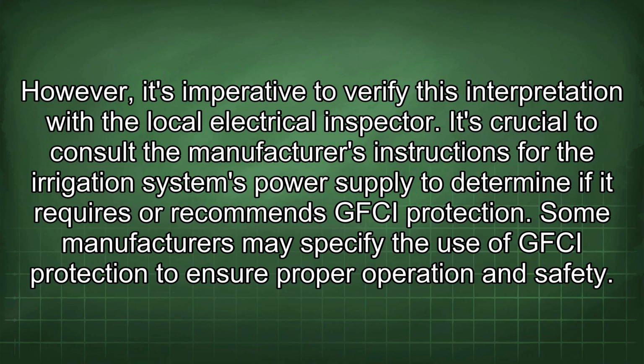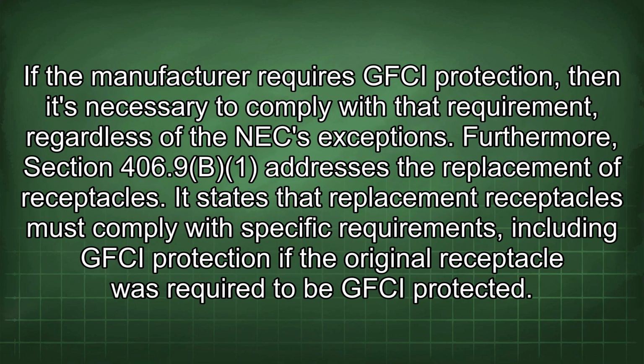It's crucial to consult the manufacturer's instructions for the irrigation system's power supply to determine if it requires or recommends GFCI protection. Some manufacturers may specify the use of GFCI protection to ensure proper operation and safety. If the manufacturer requires GFCI protection, then it's necessary to comply with that requirement regardless of the NEC exceptions.